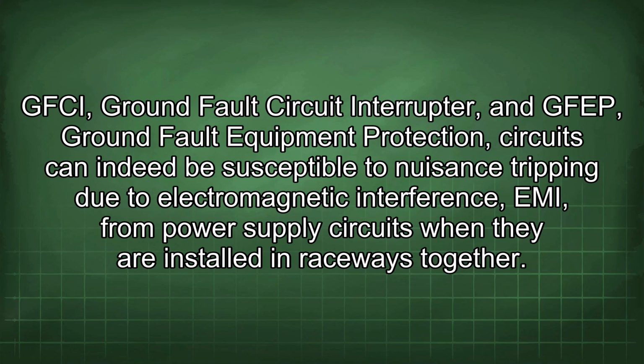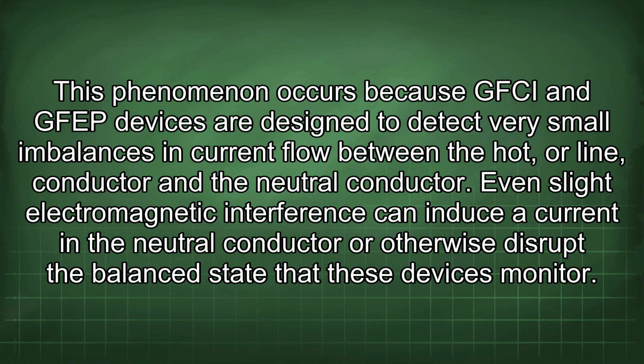GFCI, ground fault circuit interrupter, and GFEP, ground fault equipment protection, circuits can indeed be susceptible to nuisance tripping due to electromagnetic interference (EMI) from power supply circuits when they are installed in raceways together. This phenomenon occurs because GFCI and GFEP devices are designed to detect very small imbalances in current flow between the hot, or line, conductor and the neutral conductor.